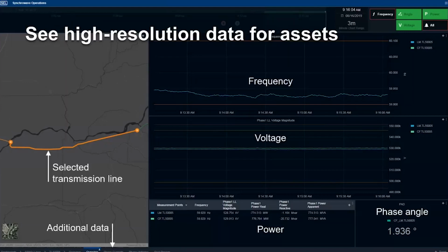Then the other question we had is, can centralized control also switch the relays from group 1 to group 2, as opposed to just staying in the same group as you showed with the FT50s or with centralized control? Yes, definitely. With centralized control, you can send different status information to the relay, so you need to program the relay. There are settings in the relay to switch between settings groups. So you can program a remote bit, which is sent from the SCADA or from the centralized control, that can switch from group 1 to group 2 or from any group to any other group. So the short answer to your question is yes, you can use the centralized control to switch between settings groups. Thanks. That was all the questions.